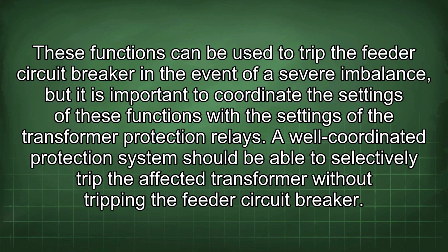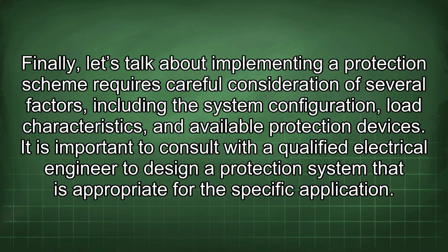These functions can be used to trip the feeder circuit breaker in the event of a severe imbalance, but it is important to coordinate the settings of these functions with the settings of the transformer protection relays. A well-coordinated protection system should be able to selectively trip the affected transformer without tripping the feeder circuit breaker. Finally, implementing a protection scheme requires careful consideration of several factors, including the system configuration, load characteristics, and available protection devices. It is important to consult with a qualified electrical engineer to design a protection system that is appropriate for the specific application.